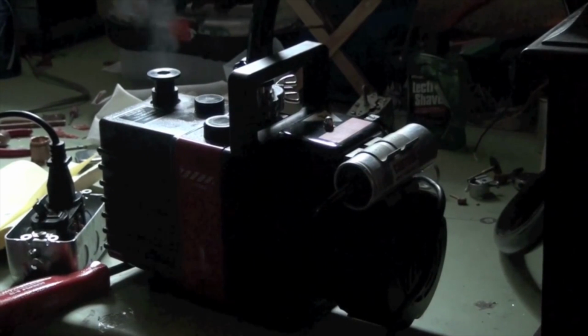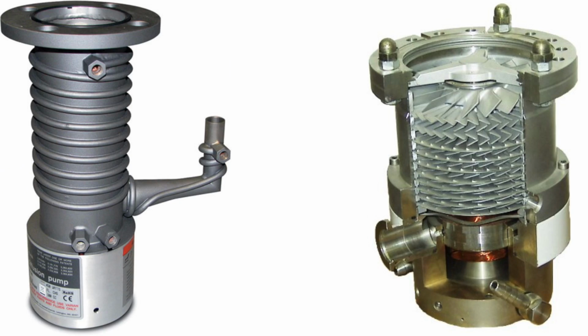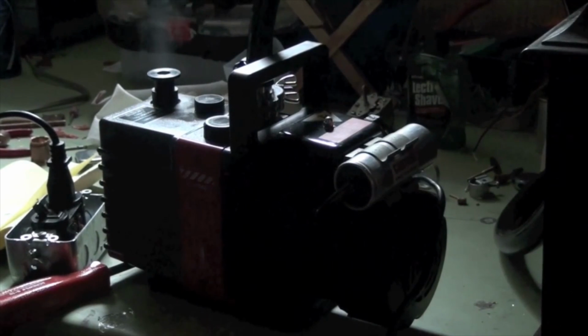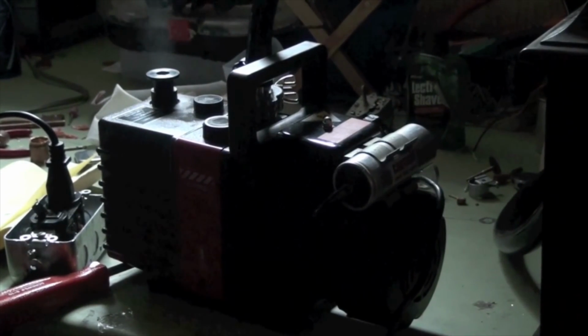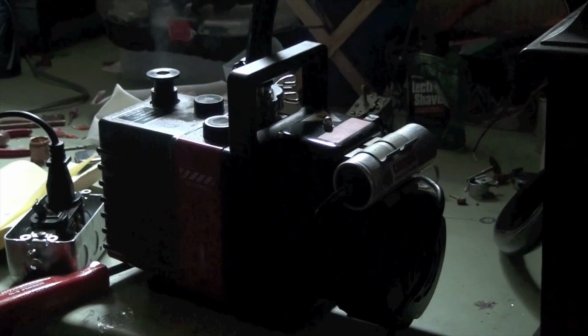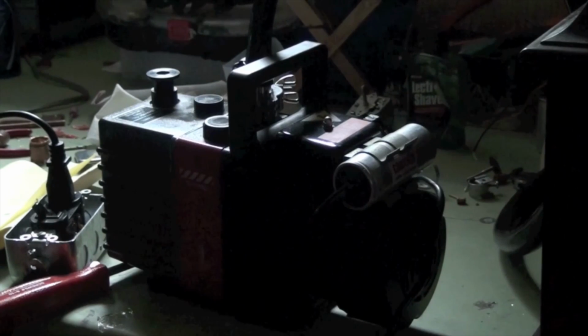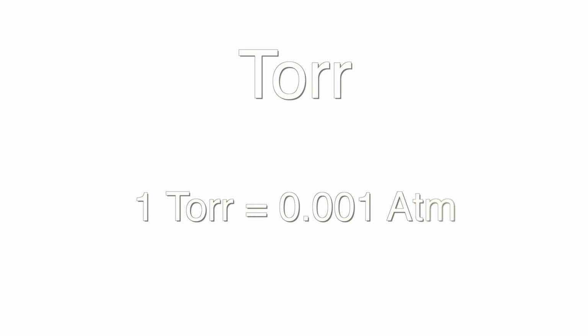To reach these pressures requires at least one special pump. The more serious the application, the more complex and powerful the pump needs to be. For the purposes of this video and learning the basics, we're only going to use a mechanical pump. In this case, we're using an Edwards rotary vane pump capable of reducing the pressure inside a chamber to at least 10 to 100 millitorr. Torr is a measure of vacuum, where 1 torr is about 1/1000th of atmospheric pressure. Our pump needs to be able to reduce the pressure to 1/10,000th to 1/100,000th of atmospheric pressure.